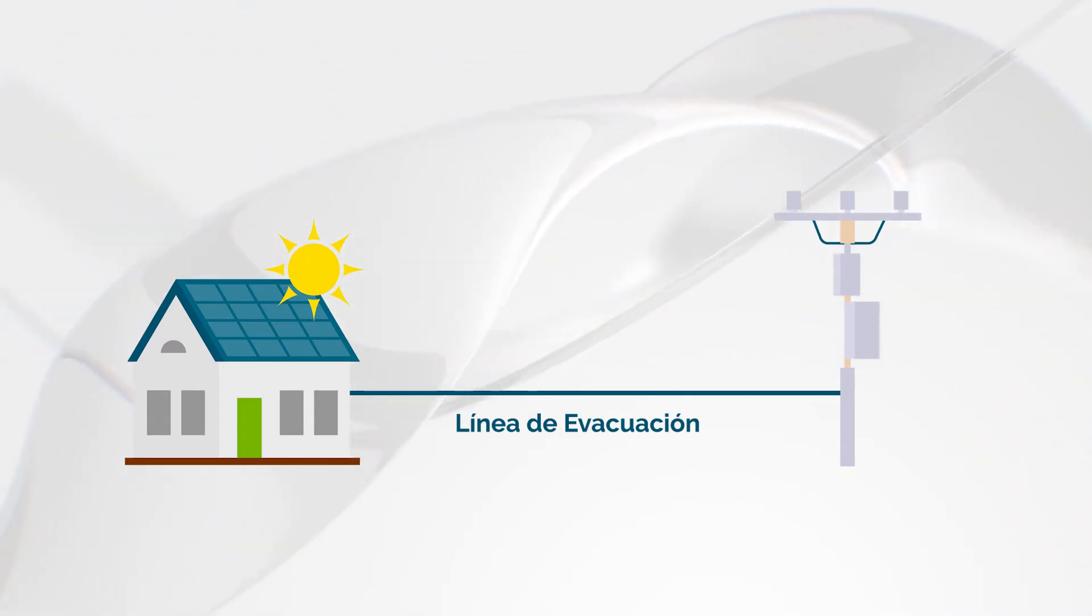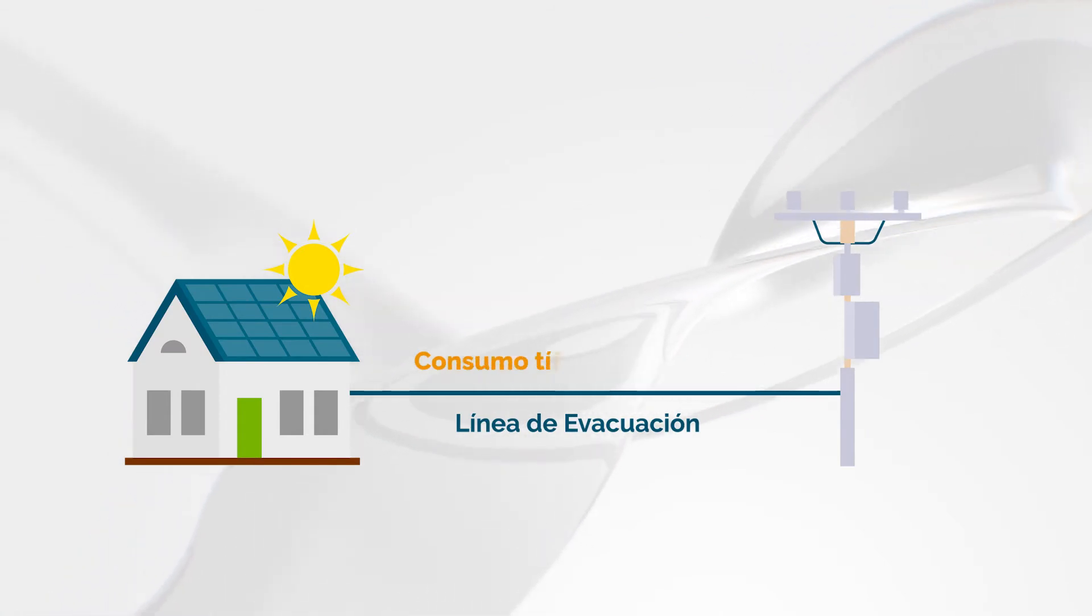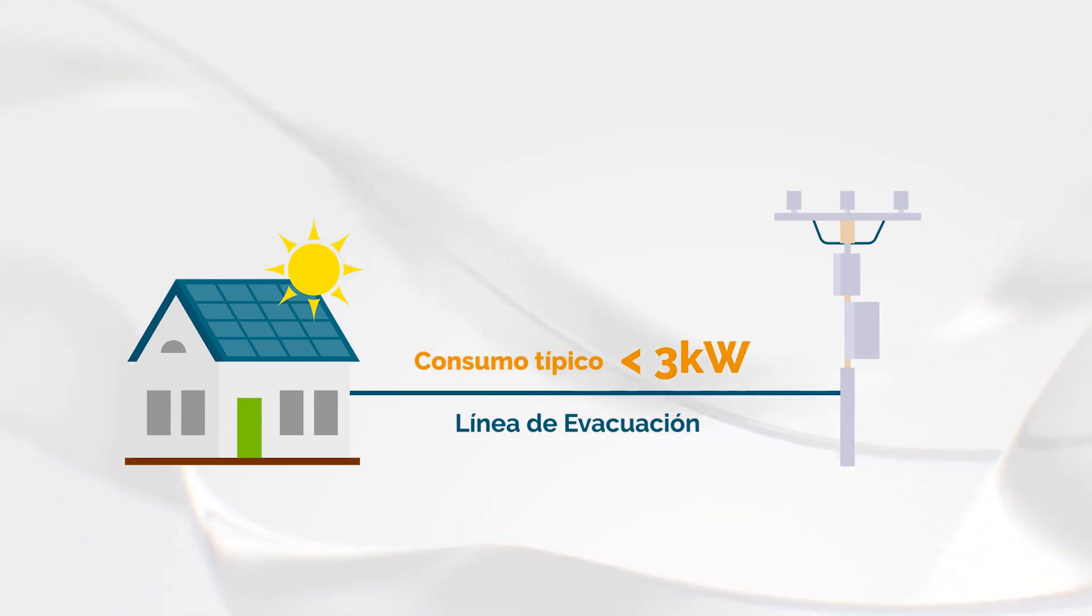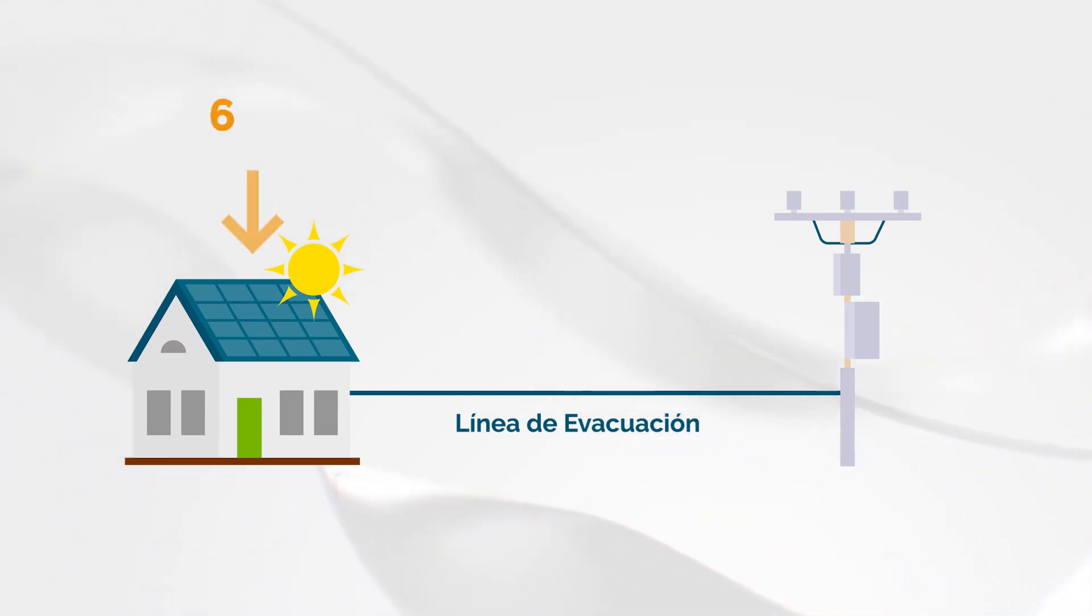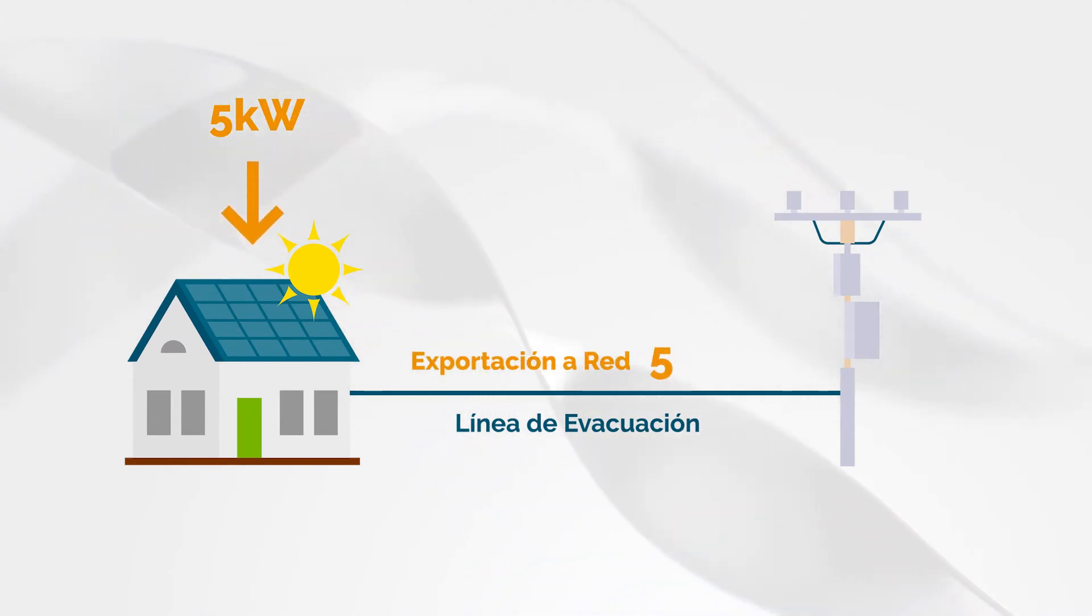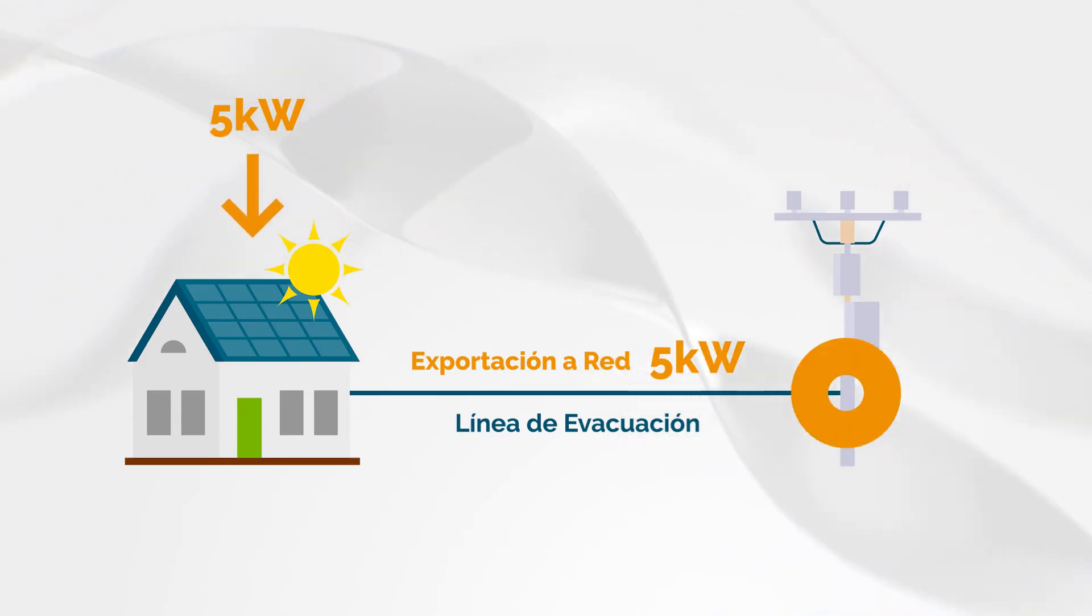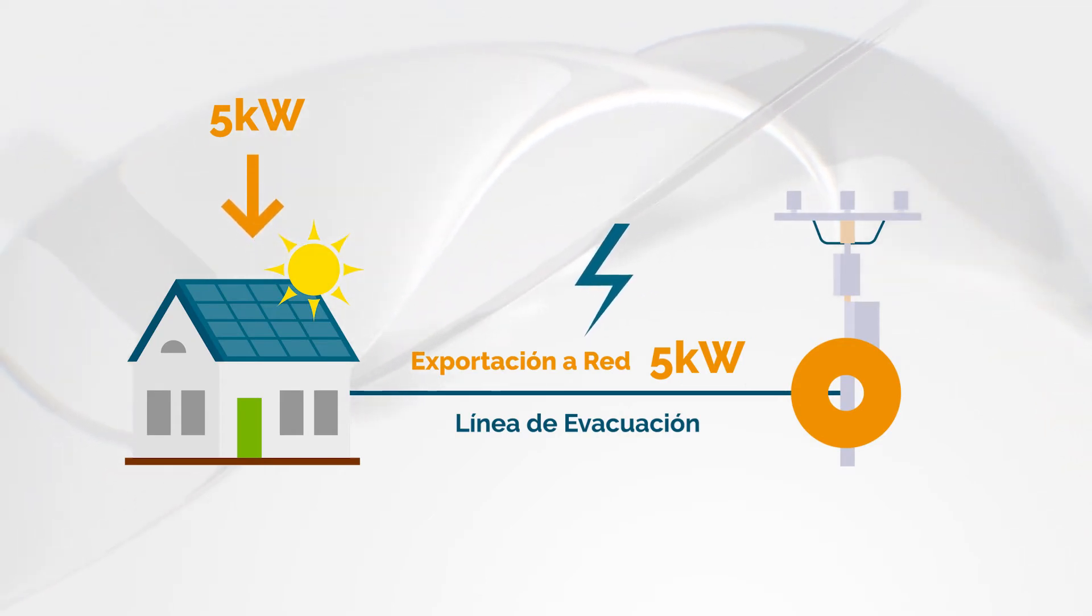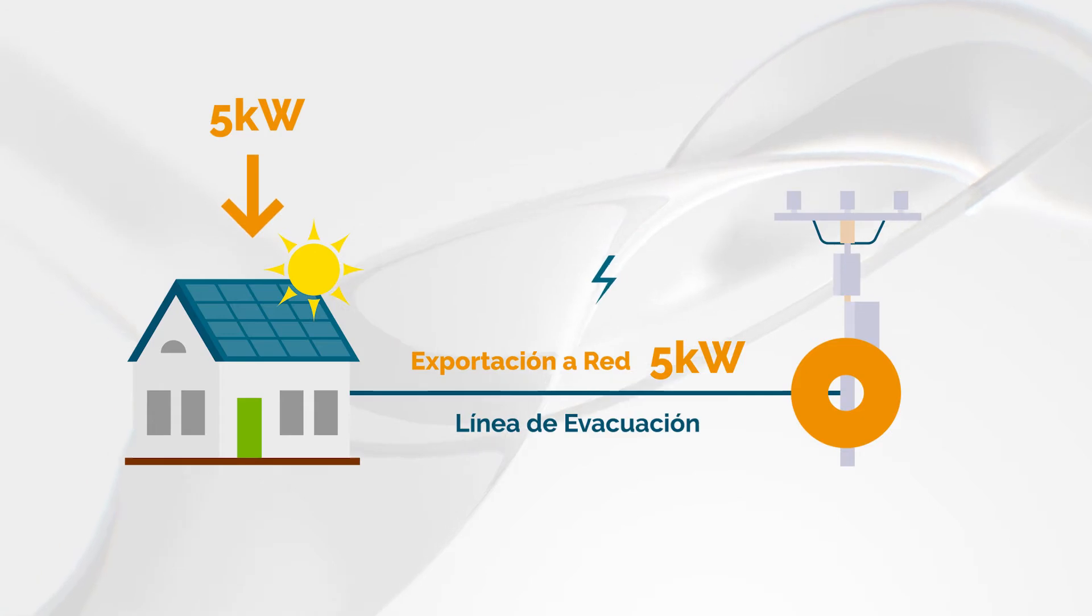These lines are sized for typical household consumption, which rarely exceeds 3 kilowatts. But if we install 5 kilowatts in solar panels and export all that power to the grid, we are creating a bottleneck. The consequence is that the voltage rises, reaching the point of activating the protections of your inverter.